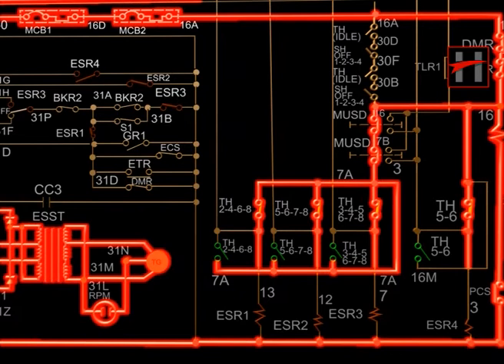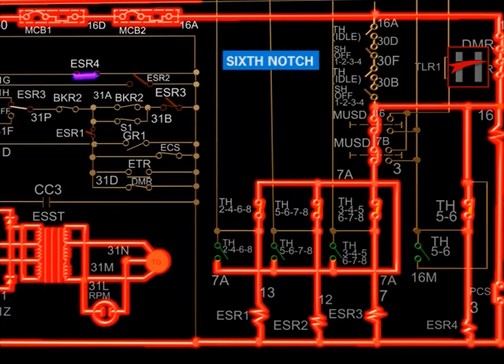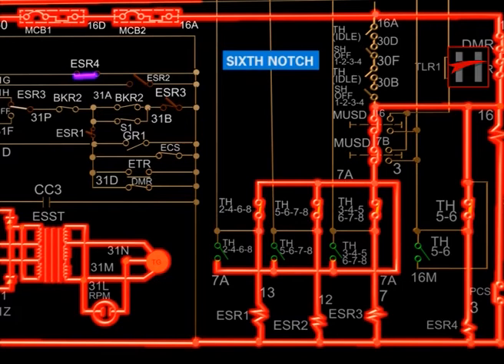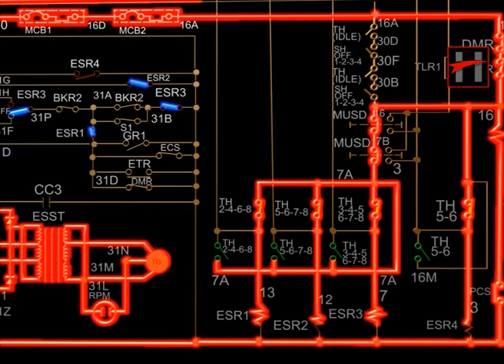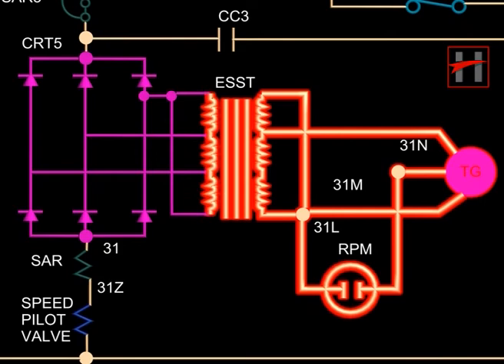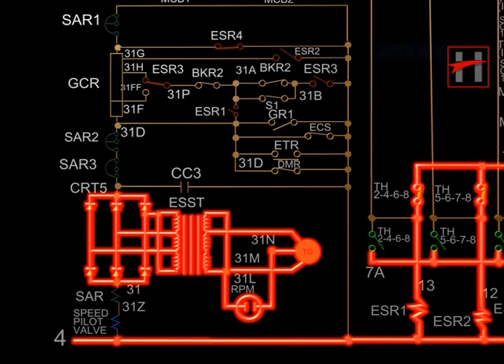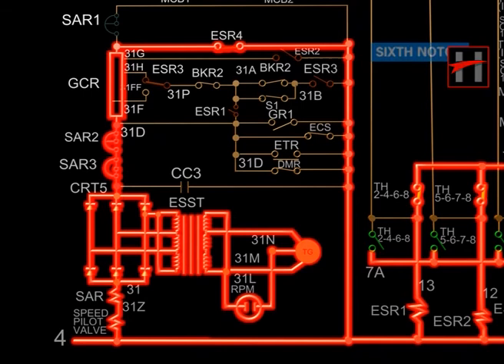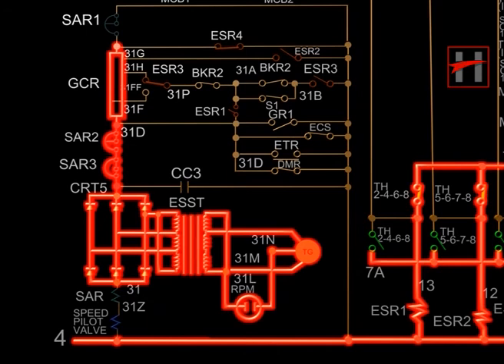In the sixth notch position, ESR-1, ESR-2, ESR-3, and ESR-4 get energized. The normally closed interlock of ESR-1 opens due to energization of ESR-1. The interlock of ESR-3 changes position from 31F to 31FF. Normally open interlocks of ESR-4 close and normally closed interlock of ESR-2 opens. The rectified output of the tacho generator flows through CRT-5, SAR-3, SAR-2, cable number 31D, 31F, GCR, interlock of ESR-4, and completes its path with cable number 4, speed coil of pilot valve, cable 31Z, SAR coil, and cable number 31.